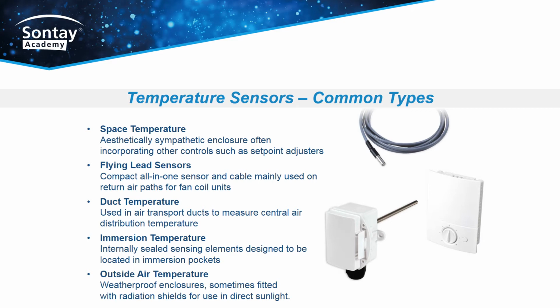For example, duct and immersion probes often look the same, but internally immersion probes contain a resin to prevent condensation forming in the sensing tube in chilled water applications. Using a duct probe instead of an immersion probe will likely result in premature sensor failure. One universal rule when selecting sensors is to try and sense the temperature at the point you are trying to control. Flying lead sensors attached to the back of a fan coil unit in a false ceiling is the compromise, to be used in large open plan office spaces.